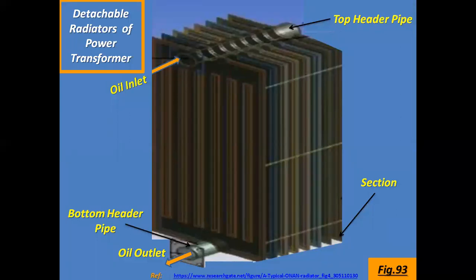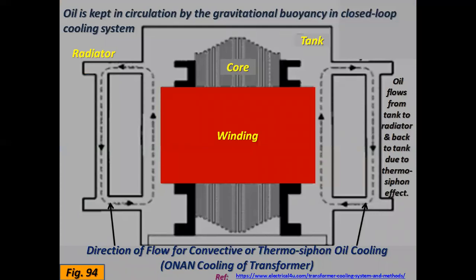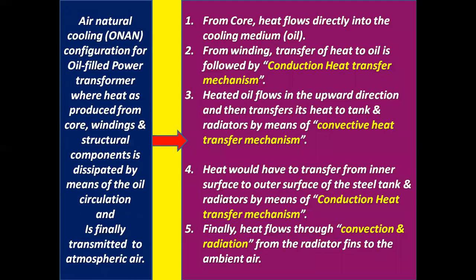Now see the detachable radiators of power transformers. Oil is kept in circulation by the gravitational buoyancy in a closed loop cooling system. This is the ONAN type cooling transformer. Oil flows from tank to radiator and back to tank due to the thermosiphon effect. Air natural cooling configuration for oil-filled transformer, where heat produced from core, windings and structural components is dissipated by means of the oil circulation and is finally transmitted to atmospheric air.